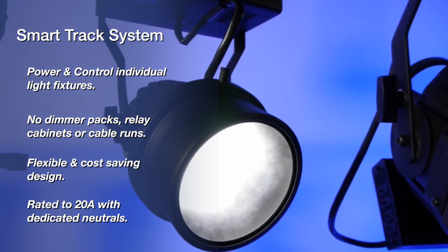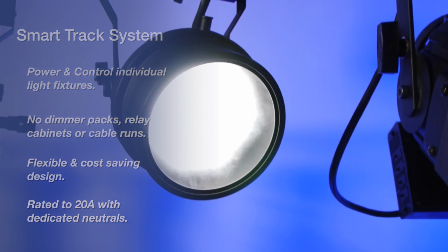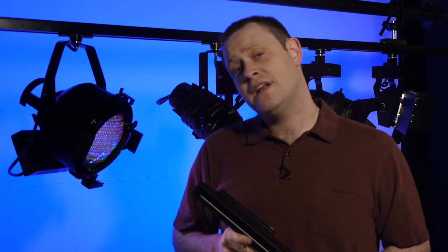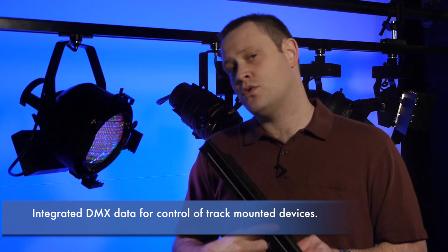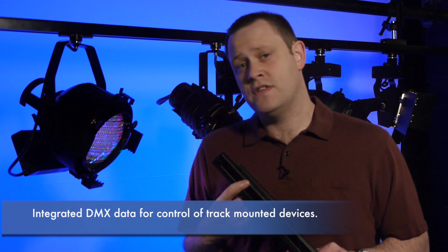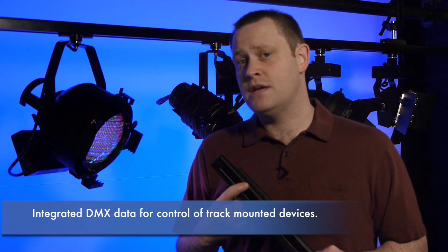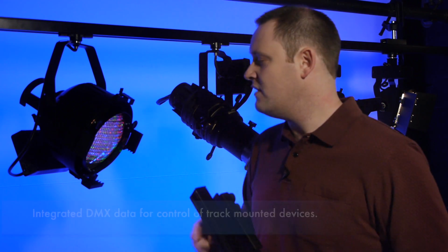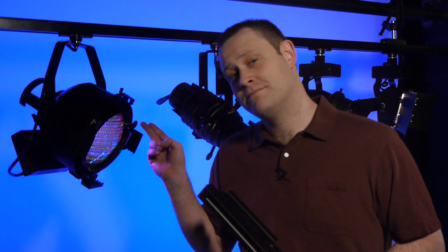SmartTrack is a specification-grade two-circuit track and data system. Each circuit of SmartTrack is rated up to a full 20 amps with dedicated neutrals. Integrated into the length of the track is a DMX or RDM data bus that allows for the individual control of onboard DMX dimmers, relays, or even the latest in LED lighting fixtures.